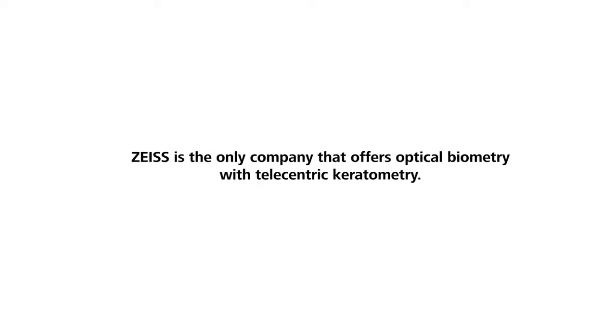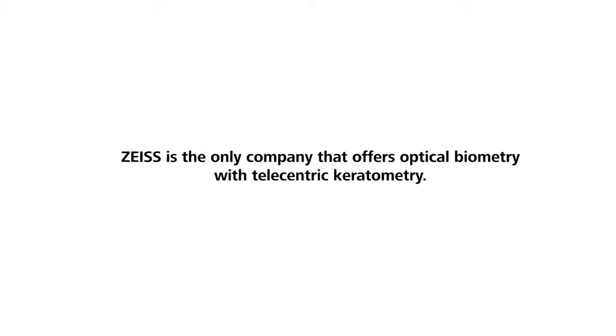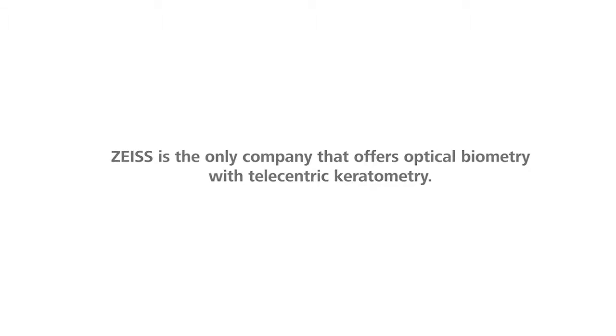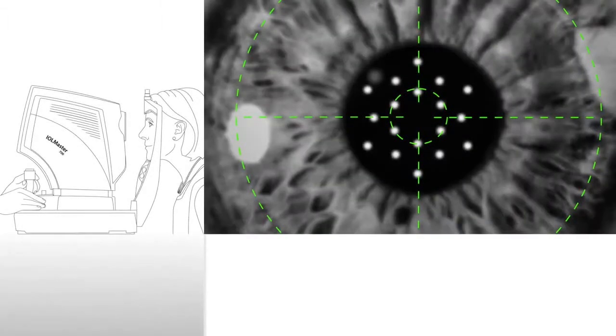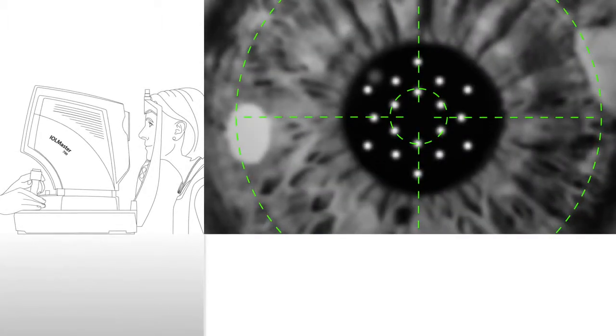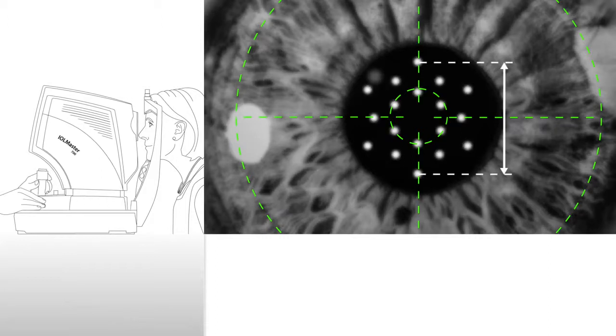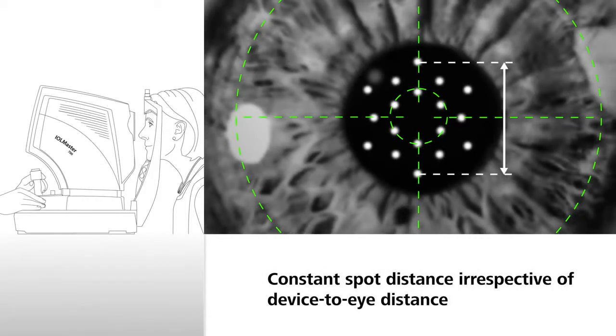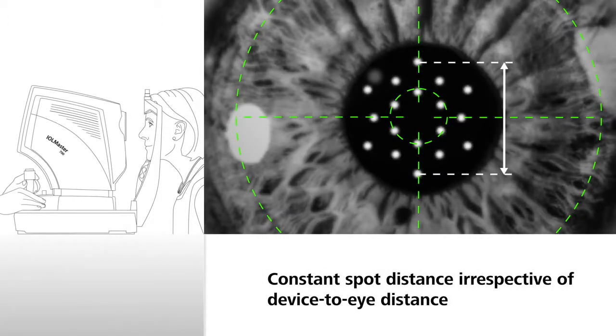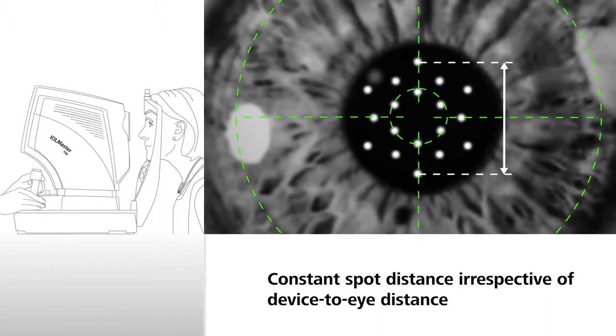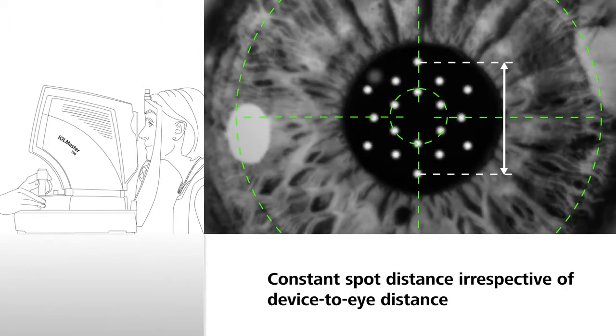Zeiss is the only company that offers optical biometry with telecentric keratometry. Telecentric keratometry of the Zeiss IOL Master 700 uses a smart optical configuration to ensure that spot distances stay constant irrespective of device to eye distance.